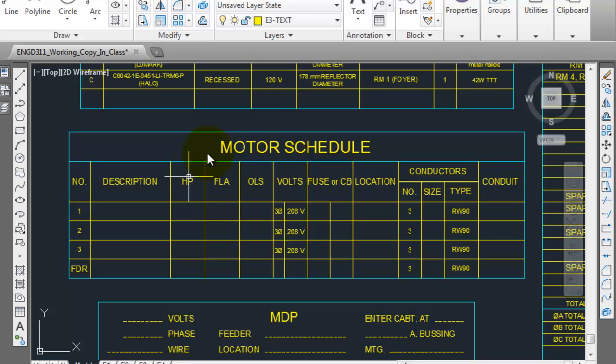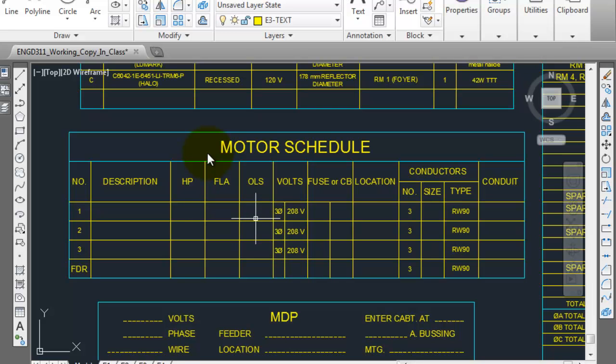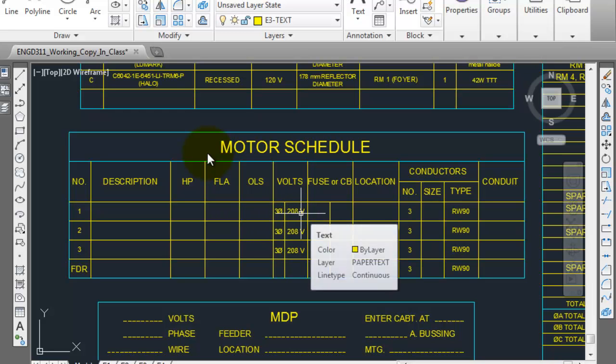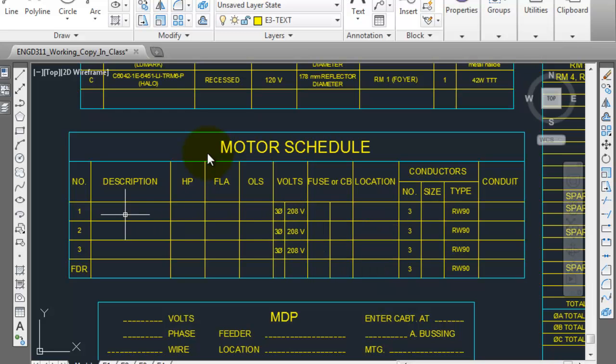And then your overload size is going to be the value that you take for your full load amps that you multiply by 1.25 or 125%. That's what you put in here. It's a three phase 208 volt motor so you just enter those numbers.